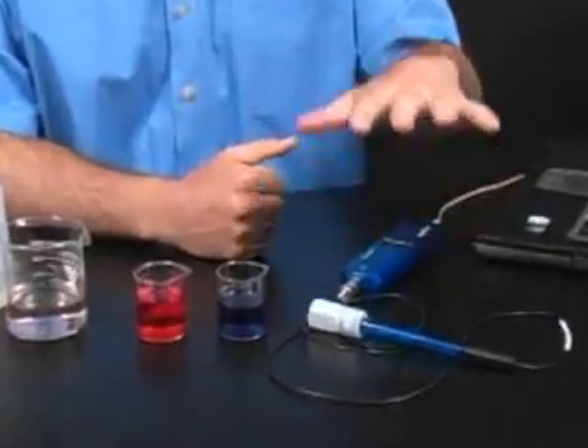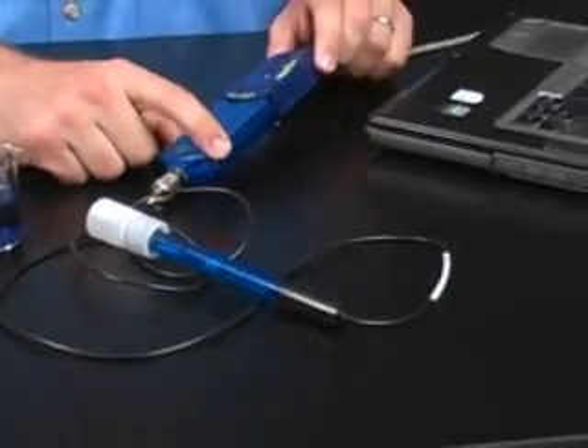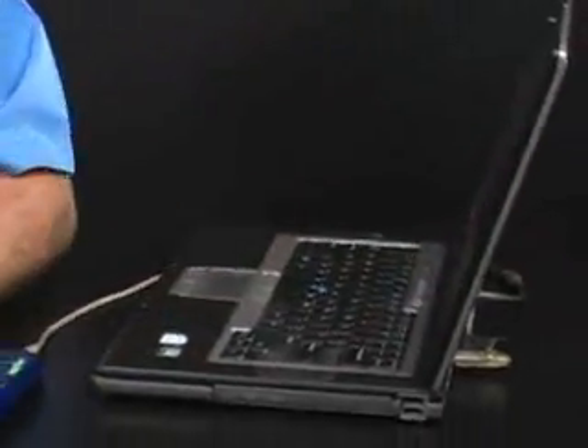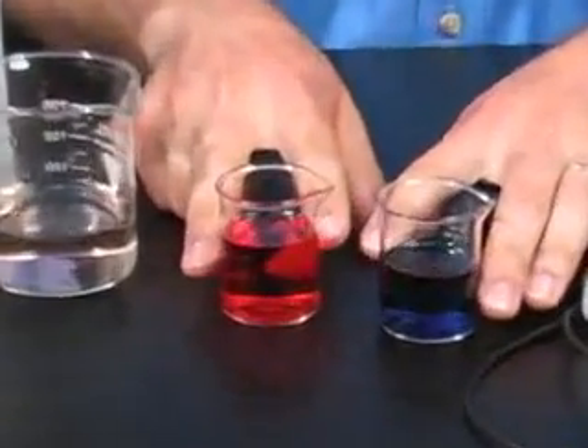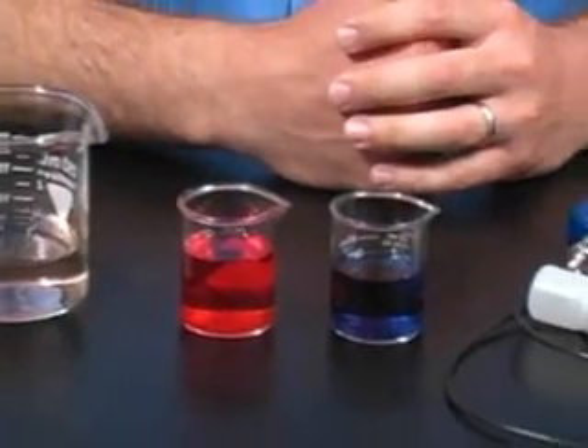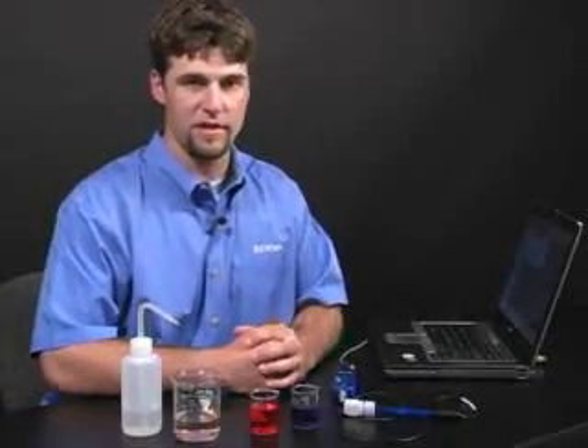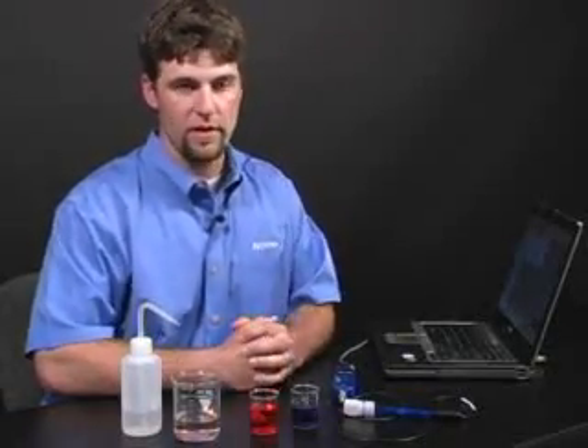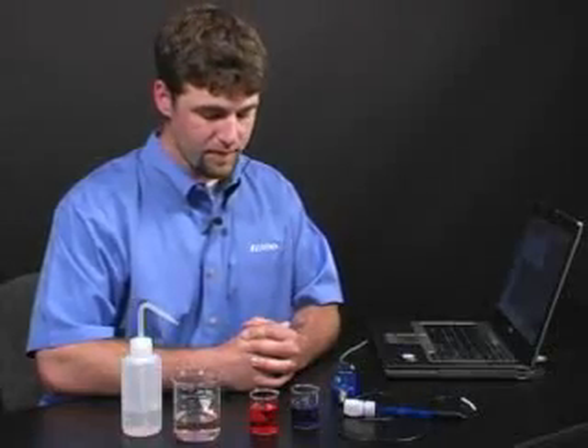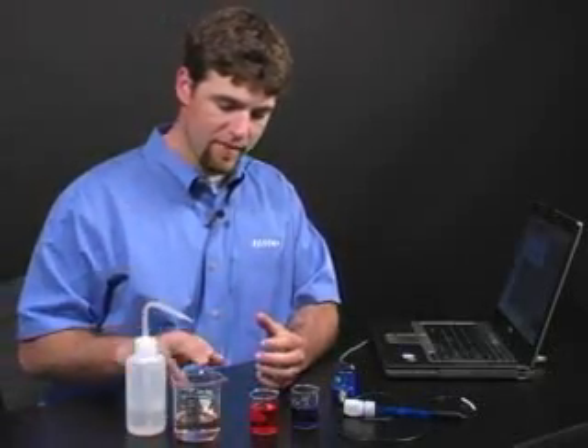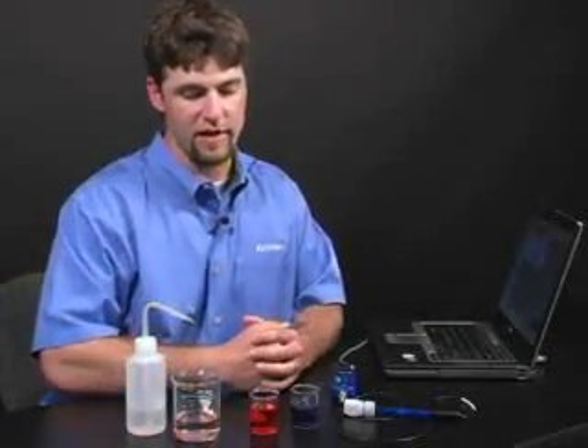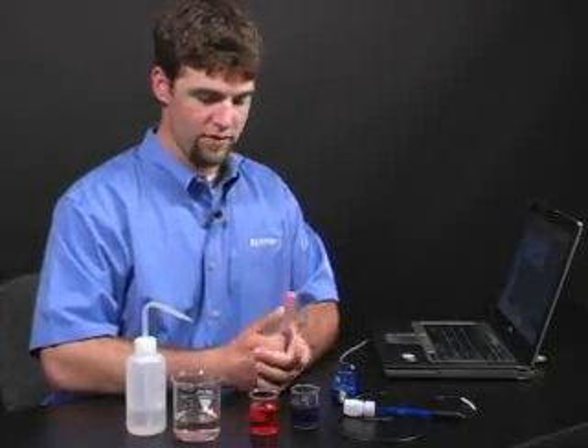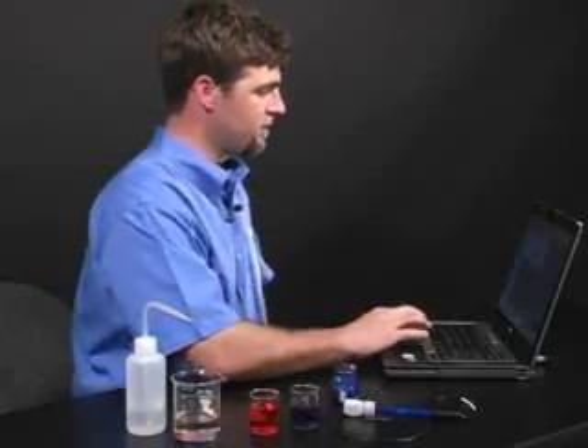Right here I have the pH sensor, which is connected to a USB link, which is connected to my computer. I have two pH buffer solutions that we will use to perform this calibration. The first, the blue one, is a pH 10 buffer solution. The red one is a pH 4 buffer solution. I have here a rinse bottle and catch basin to rinse the probe in between placing it in either buffer solution. So let's go ahead and get started in DataStudio.